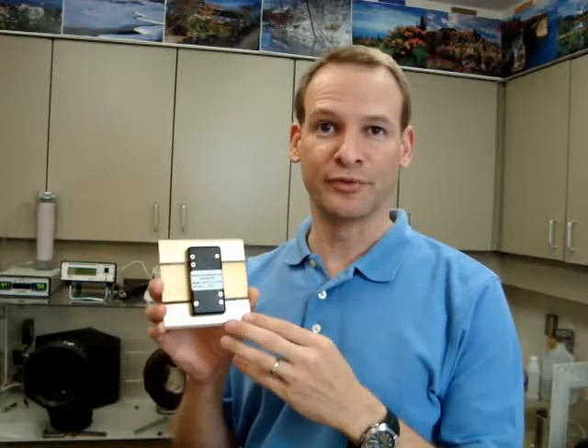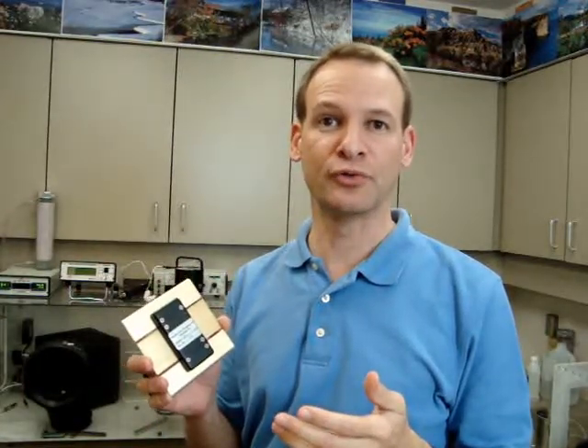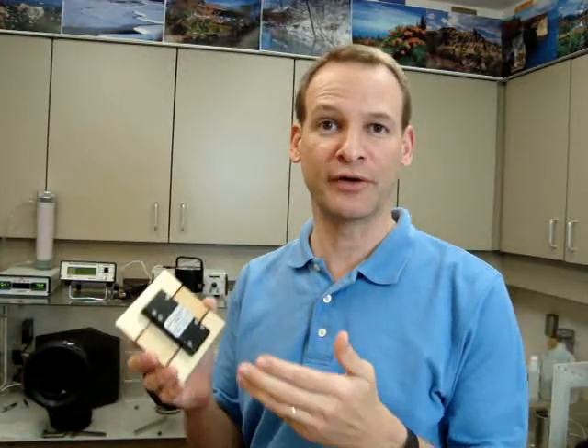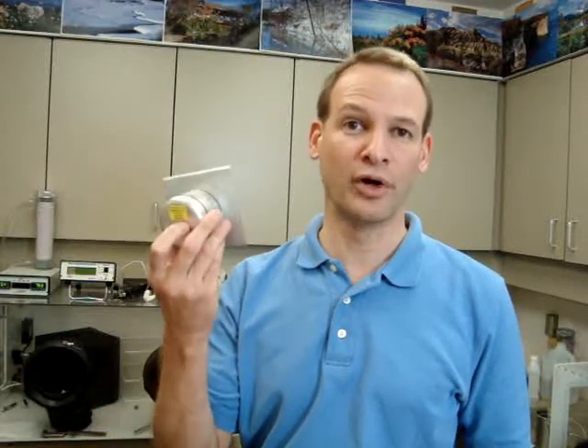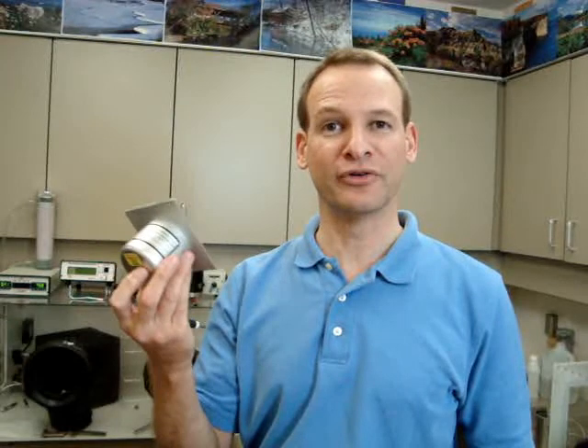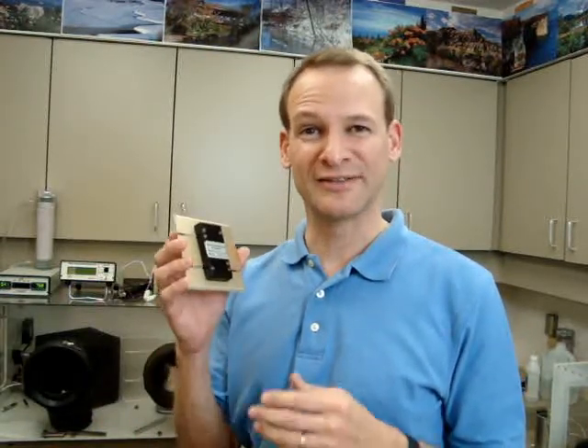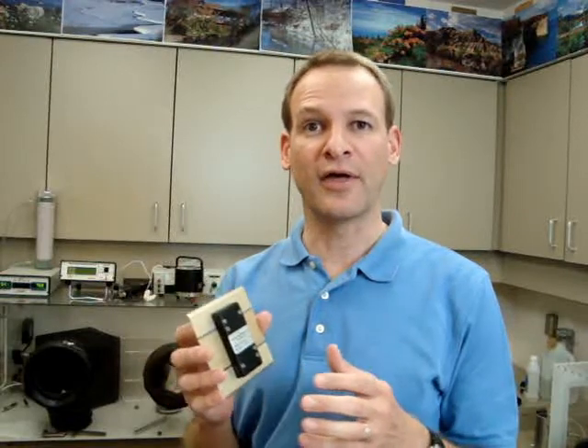the STM-2. The purpose of this video is to explain the function and purpose of the STM-2. Now keep in mind, many of the points we're going to mention here also apply to the STM-1, which is an older model and is now obsolete. Now STM-2, what does it stand for? Well, it stands for the System Test Module. It's used to test and verify that the 406 static decay meter is functioning properly, that it's within balance.